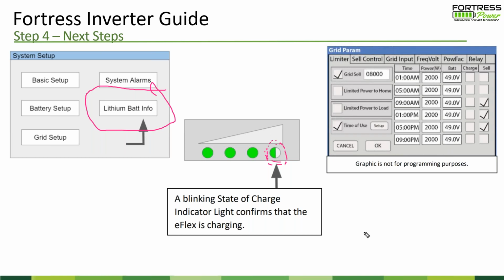Before you leave site, you want to make sure that all batteries on site are charging and or discharging, to confirm that the battery has been properly commissioned. On the eVault, just look at the screen. On the eFlex, you'll see one of the state of charge lights blinking to indicate that the battery is charging up. If you see all four eFlex batteries on site accepting a charge, you have successfully commissioned the system.